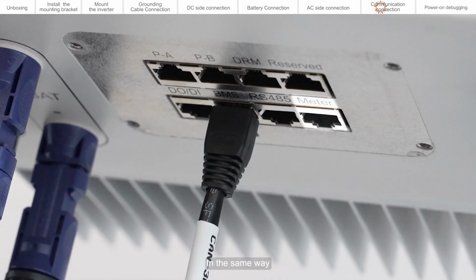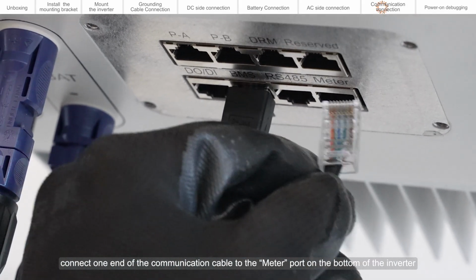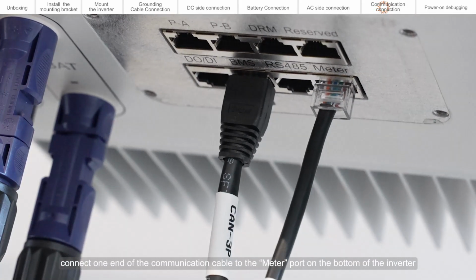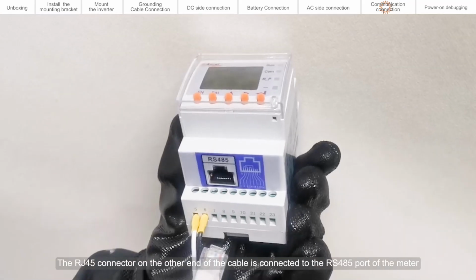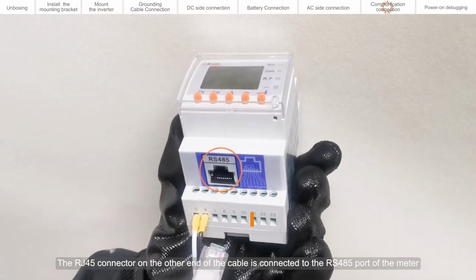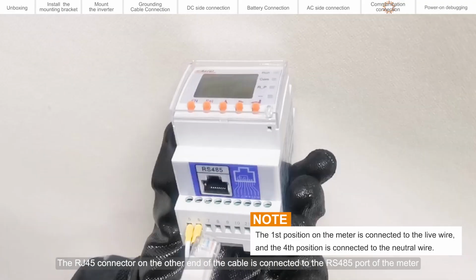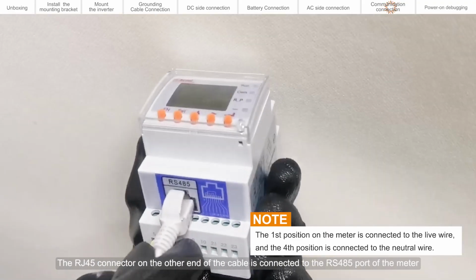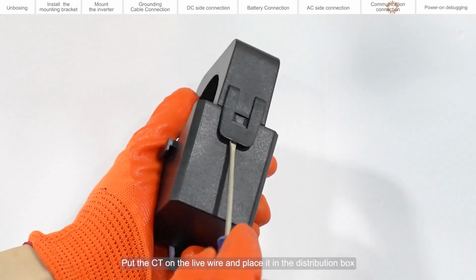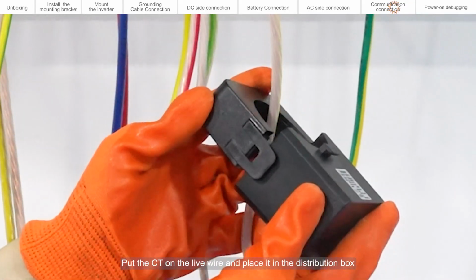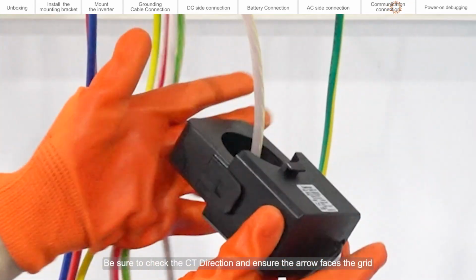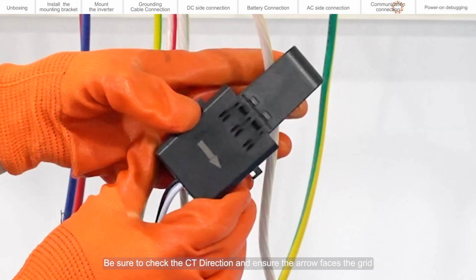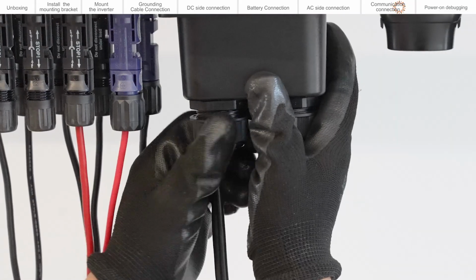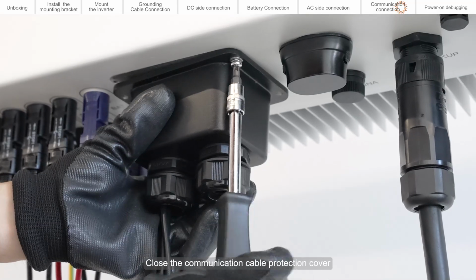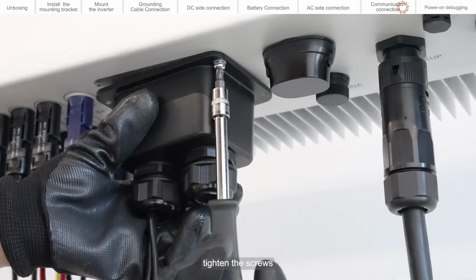In the same way, connect one end of the communication cable to the meter port on the bottom of the inverter. The RJ45 connector on the other end of the cable is connected to the RS485 port of the meter. Put the CT on the live wire and place it in the distribution box. Be sure to check the CT direction and ensure the arrow faces the grid. Close the communication cable protection cover, tighten the screws.